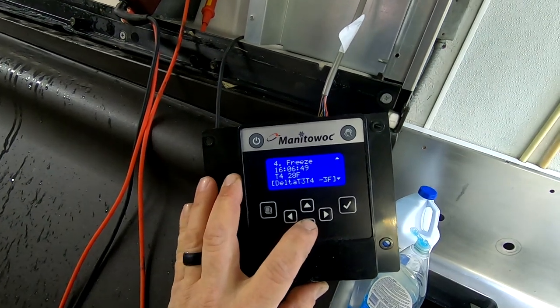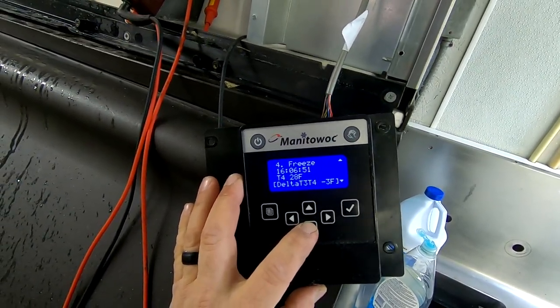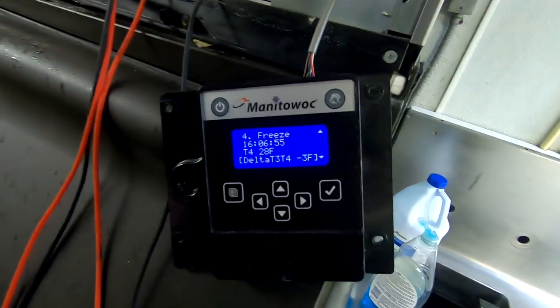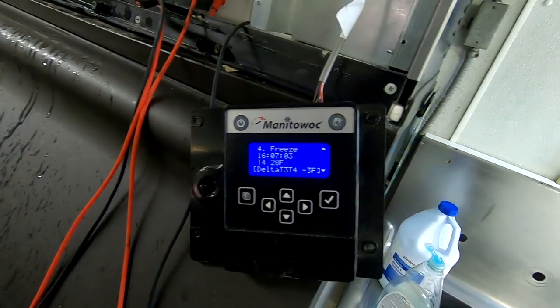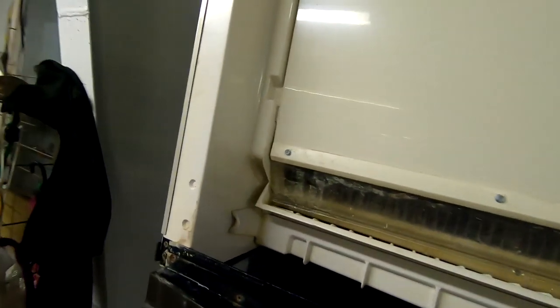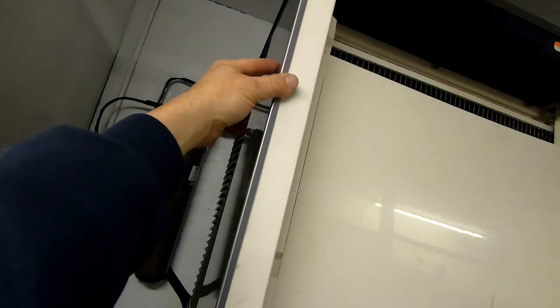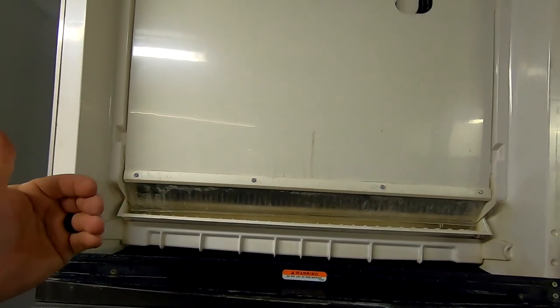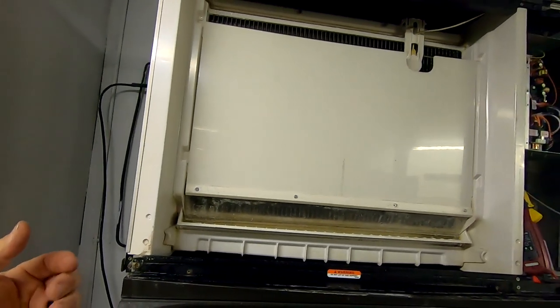That should retract the way it's supposed to. Yeah, it might be our hot gas: 135, 25, and 28. That's our evaporator, so this is a single evaporator system. So I believe this one's going to stay pretty accurate to the usual. Smaller units generally you want less than a seven-degree delta T across your evaporator.